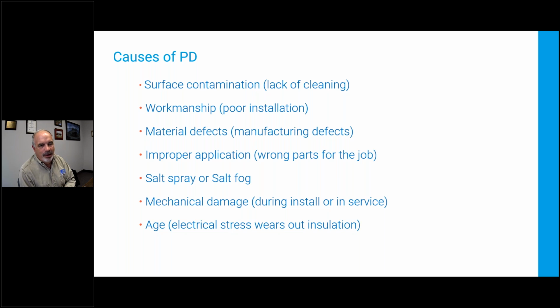Salt spray and salt fog. If you live on an island and you have a power system, I feel bad for you. It's unavoidable that when you get salt spray and salt fog in your power system, you're going to have problems. And some of these island nations and some of these refineries on the Gulf Coast and on offshore platforms, they've got a tough job. I don't envy them at all. That's a big problem. Mechanical damage, things get damaged. For those of you who aren't in the United States, it's a thing we do. We shoot out insulators with a high-powered rifle. It happens, and I don't know why we do it, but we do it. Any kind of mechanical damage can change the field distribution. And then age, things do wear out. Electrical stress does impact insulation, and over time you can get a wear-out mechanism. That can take decades, though.